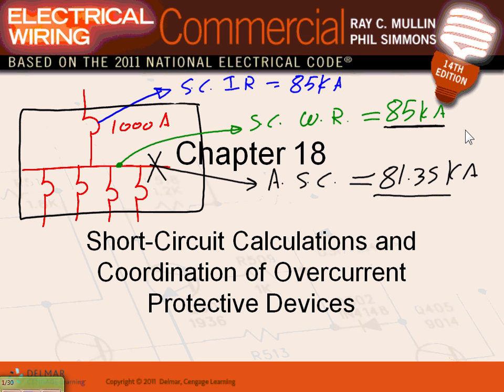Any question, guys, about these 3 values? So yesterday we talked about the blue value, the interrupting rating for equipment. Today we'll talk about the withstand rating. Most of the time, the withstand rating is equivalent to the interrupting rating of the equipment. That makes sense, right? Because you don't want to interrupt higher than what the equipment can handle, right? If my equipment can handle 85, why should I limit my interruption to 65, for example?